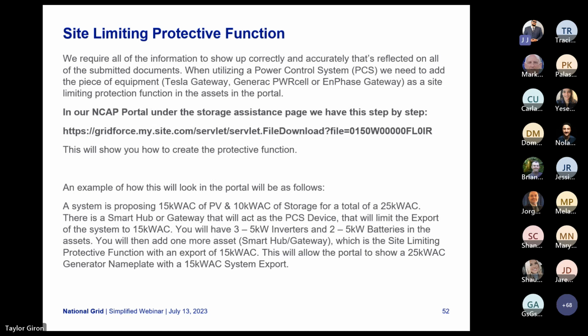And I have a quick example here of how, if you have a 25 kW AC system but would like to avoid group study, you can add some sort of smart hub or gateway utilizing PCS that will only allow 15 kW AC of export. So by adding that additional asset in the portal, it'll show as a 25 kW AC generator nameplate, but it will only show as a total export of 15 kW AC aggregate.